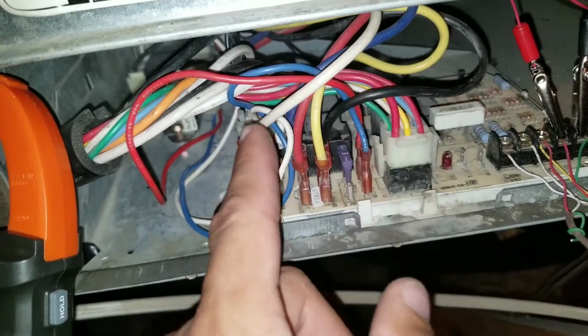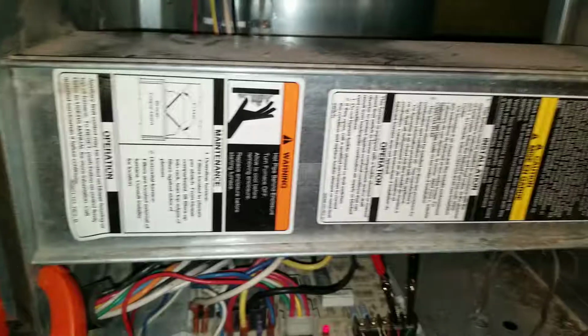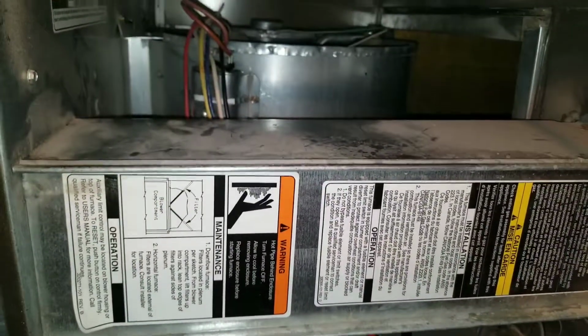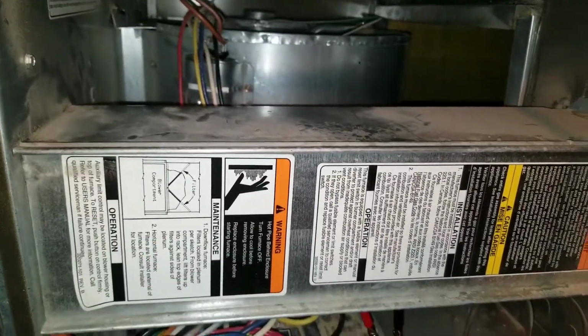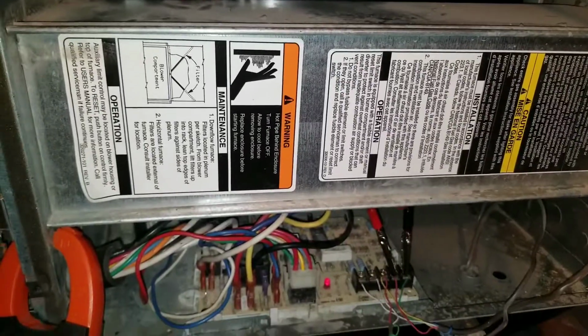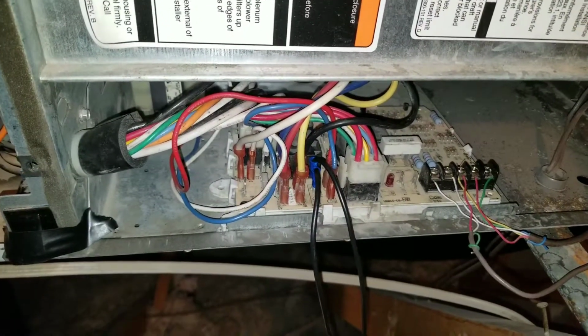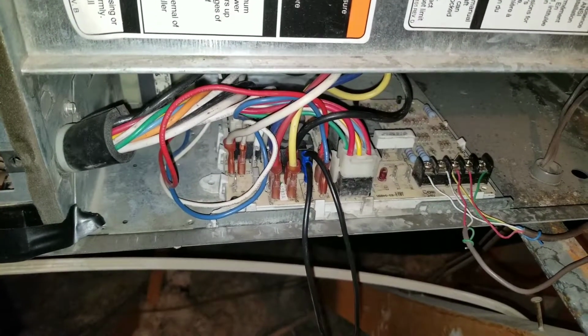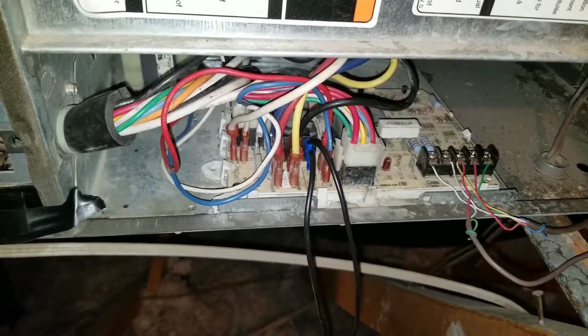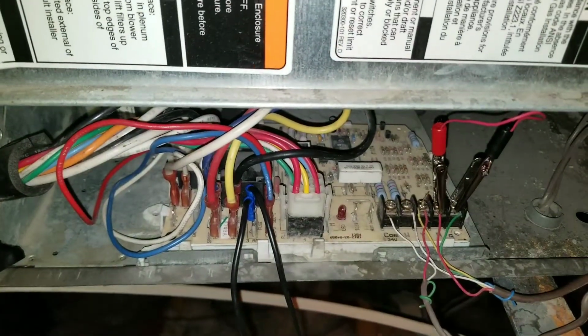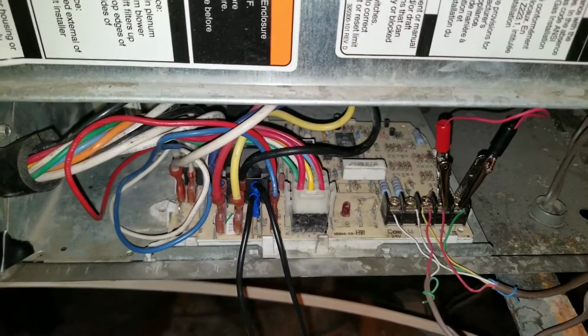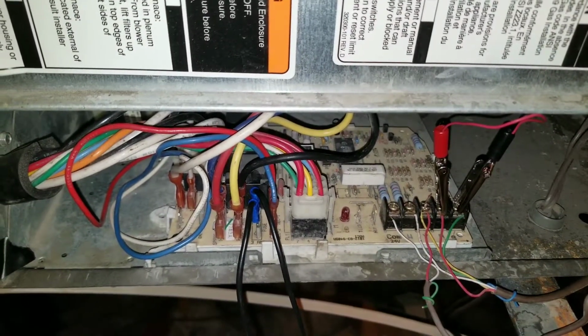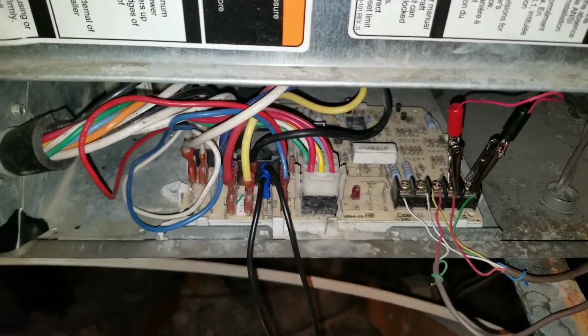Here I tied my wires coming from my blower back to the board. Turn our system back on. This method is extremely beneficial when you're trying to find a short in your system. Right now, I've purposely created a short in my condensing unit, and I'm going to test the system.